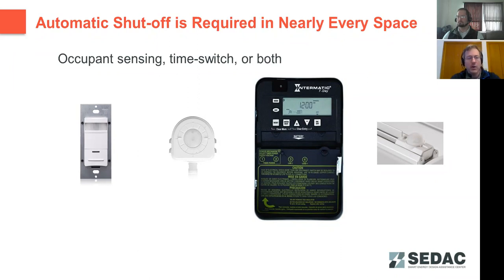So right off the bat, we call out that automatic shutoff is required in nearly every space. This could be done either with occupant sensing devices, time switch controls, or a combination of both. The code does have language that allows you to use occupant sensing devices in lieu of time switch controls for areas that the code states need time switch controls. However, it does not go the other way around. So if the code calls out that you need occupant sensing devices, you can't use time switch controls to meet that requirement.